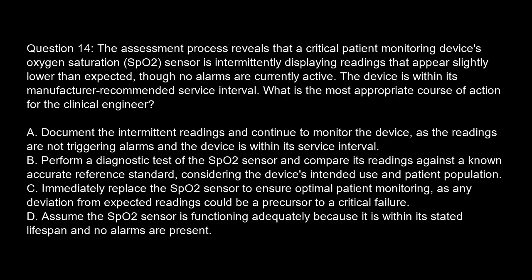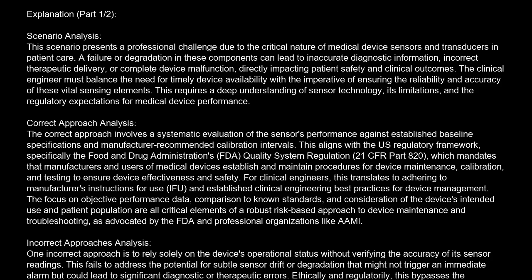Option C. Immediately replace the SpO2 sensor to ensure optimal patient monitoring, as any deviation from expected readings could be a precursor to a critical failure. Option D. Assume the SpO2 sensor is functioning adequately because it is within its stated lifespan and no alarms are present. The correct answer is B. Perform a diagnostic test of the SpO2 sensor and compare its readings against a known accurate reference standard, considering the device's intended use and patient population.